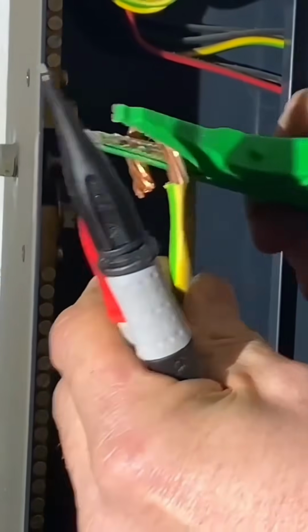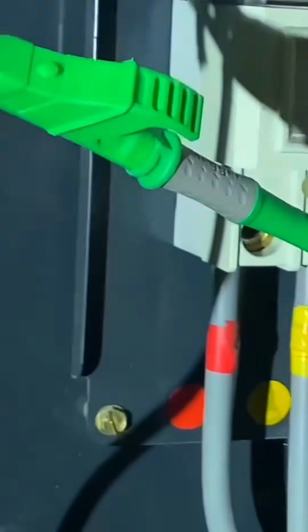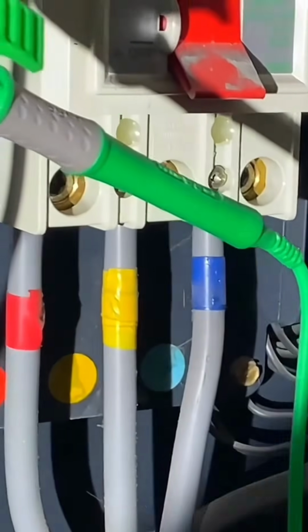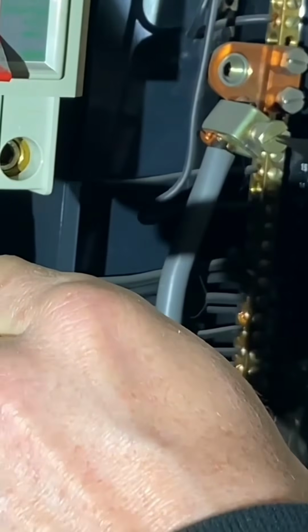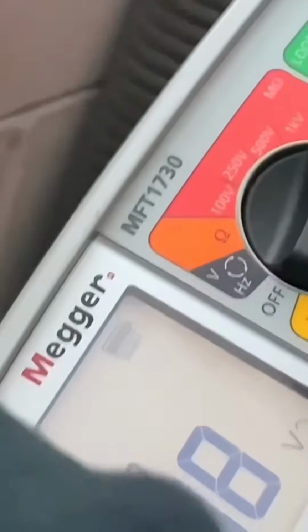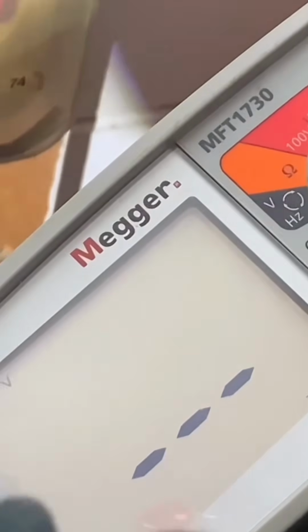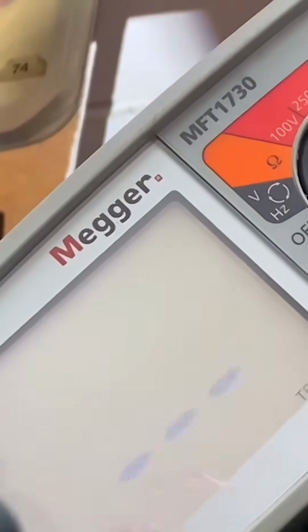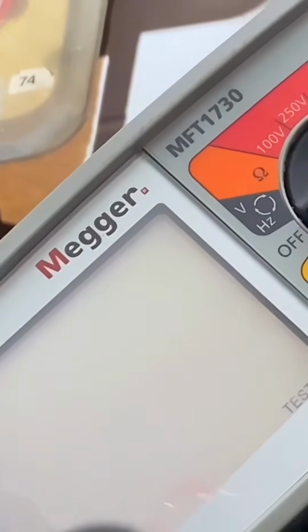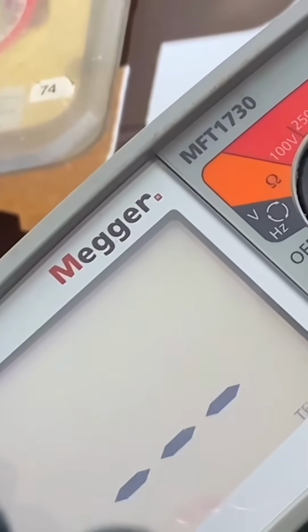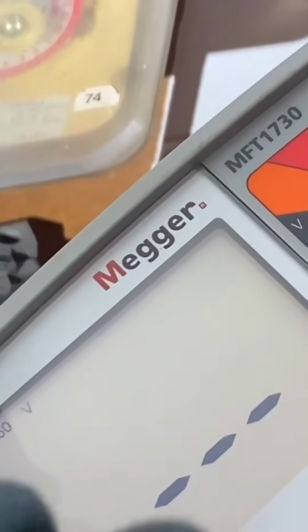Right, okay, do you want to probe on for me? Disconnected earth there, so we'll get a nice good connection onto there. And then we've got the neutral terminal here, yep. And then we've got our 3 phases there, so let's just move that one out of the way. Again, it's an automatic test, so go onto the neutral terminal first, and then we'll just probe onto the first line conductor, and as you can see there, the machine has automatically detected voltage, and it takes a few seconds because we're on the low one. Yep, that's fine. So we'll persevere and wait for our result.